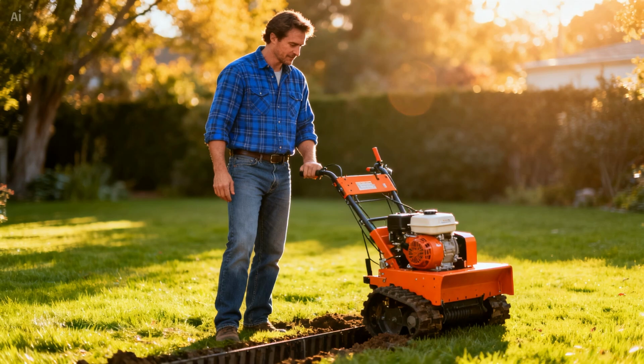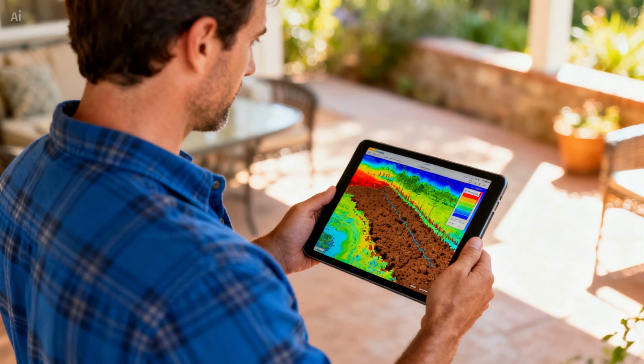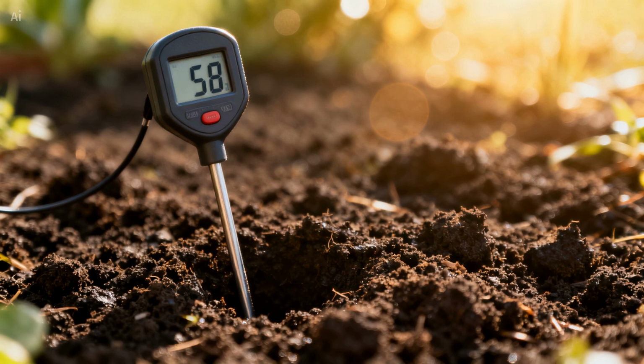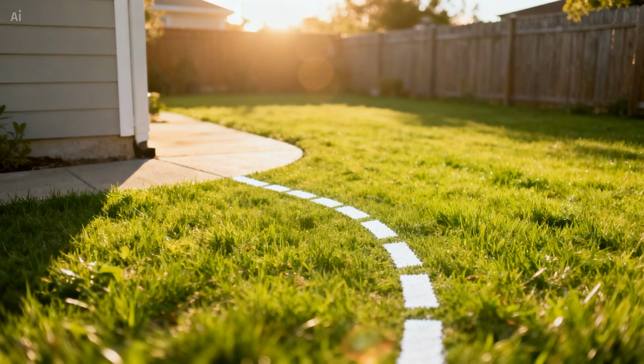The installation process is straightforward enough for any homeowner with basic comfort operating a rented trencher or sufficient determination with a shovel. Start by checking your local ground temperature. Contact your county agricultural extension office or search the USDA soil temperature database for your region. If the ground temperature at 6 feet depth is between 50 and 62 degrees, your property is well suited for earth tube cooling. Plan a trench route from the north or east side of your property to the building foundation.